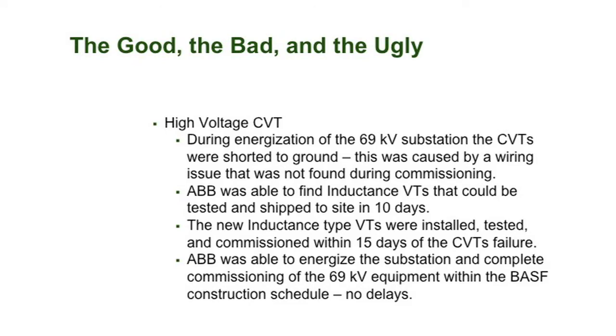First Energy came in, they pulled in their switches, confirmed we had power on the system, went into the microscada system, looked at the meters to determine the incoming voltage, and found out that instead of 69 kV, we were showing 29 kV. So we realized we had a problem.